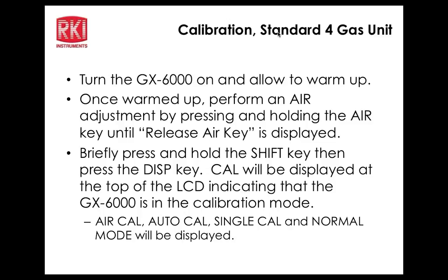We'll go down and do air cal here. Press power enter. I'll press the air key, hold the air key again. Adjusting zero, release air key. Zero adjusted. Bob actually pressed the button and selected auto cal, which is exactly what we wanted to do anyway.